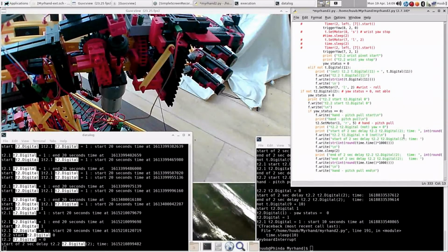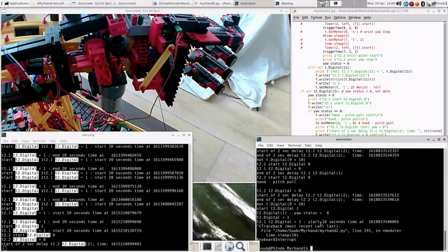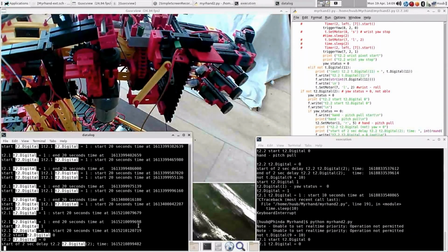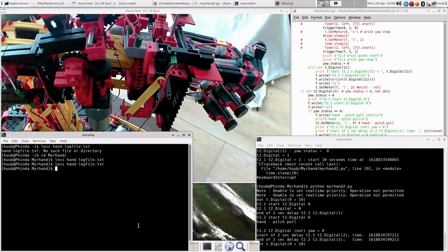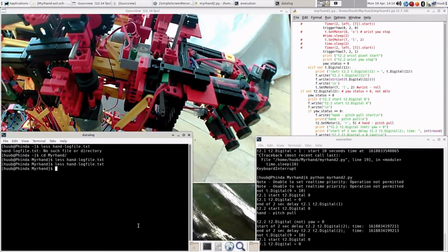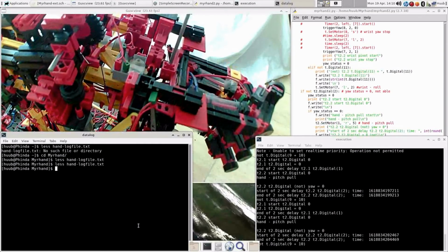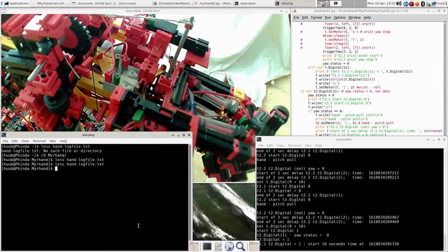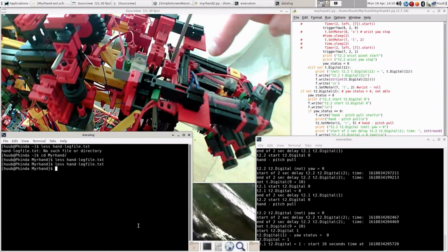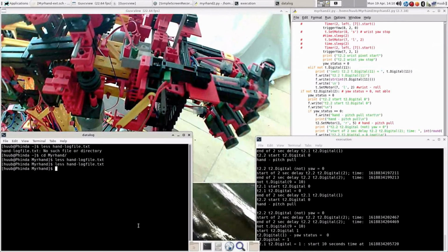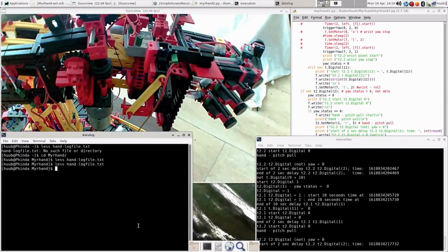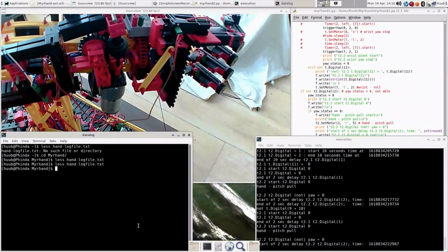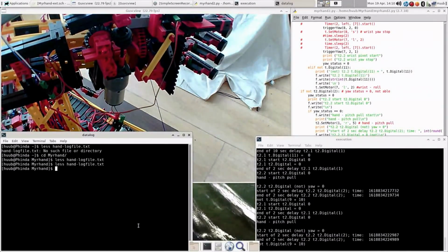So let's start once again and see if that does make a difference somehow. Because right now it's pulling and now it's releasing again. And when you look at these switches, I have to have a delay. That was obvious, and I had it at 30 seconds, which did make a difference somehow.